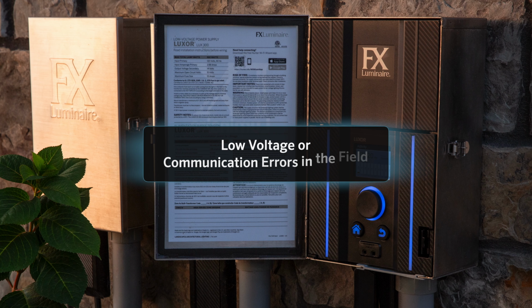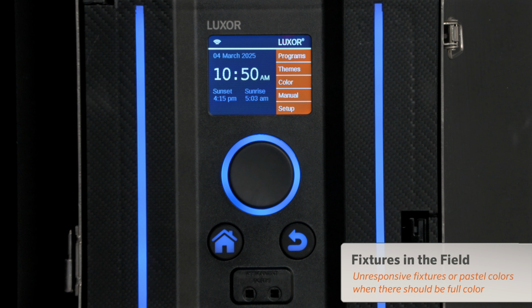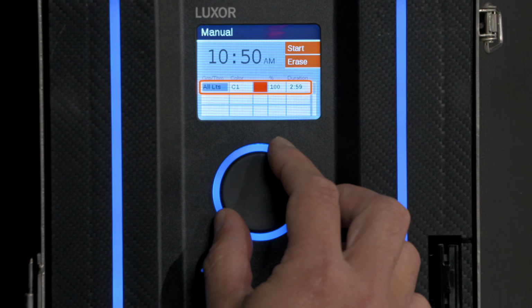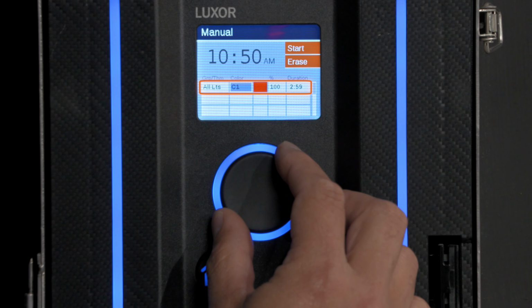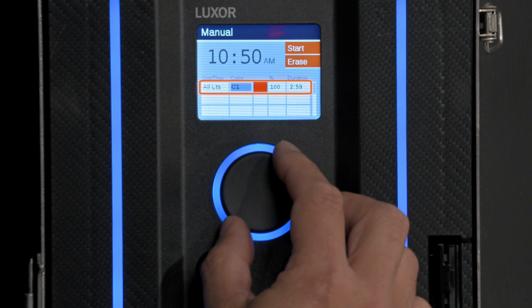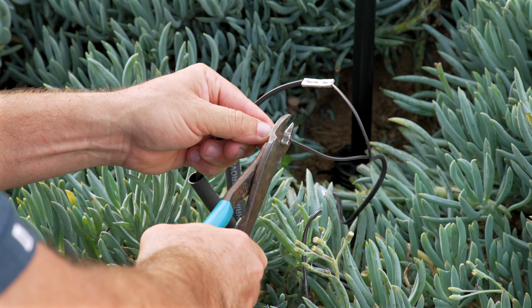This section covers low voltage or communication errors in the field. You may see the fixture turning all white and not responding to commands, whether it be turning on a color or changing intensity. Colored fixtures may also display pastel tones instead of the selected color. To start, go to Manual, then All Lights. Select a color. Make sure that it's a deep, pure color at 100% intensity. Select a time. And press Start. Since there is a faulty wiring connection in the field, the selected red color shows pink instead of the bright red color we selected. You will need to repair the wiring in the field.